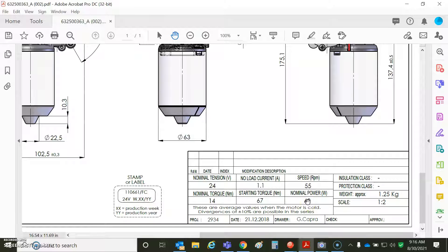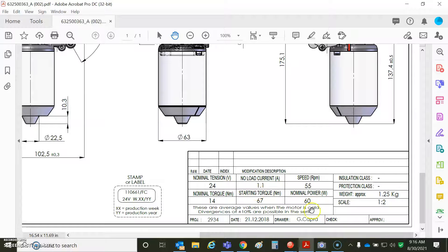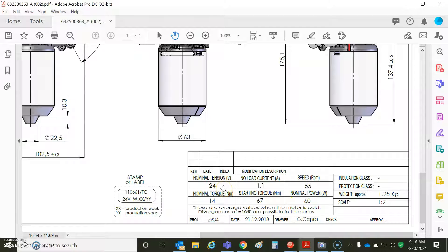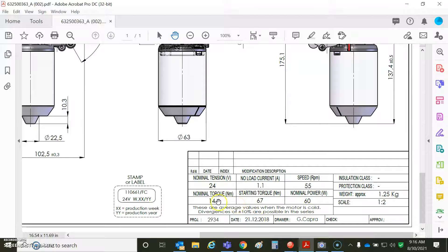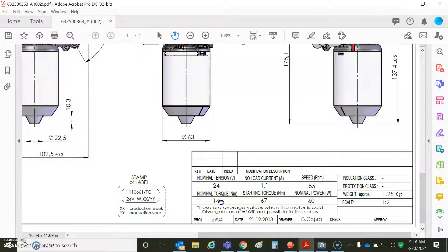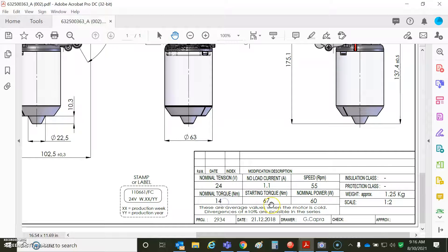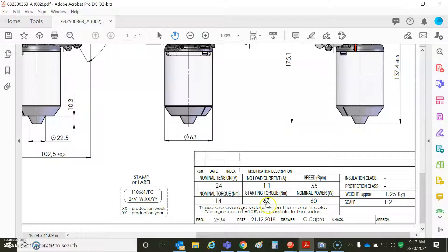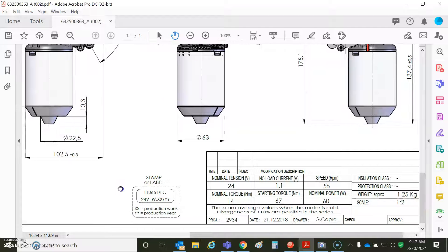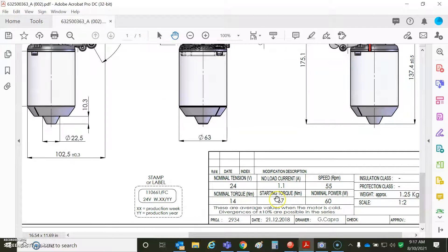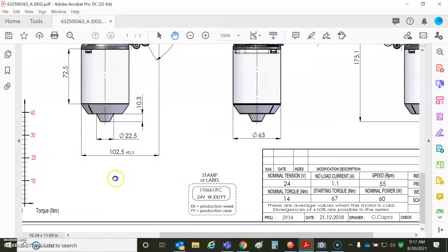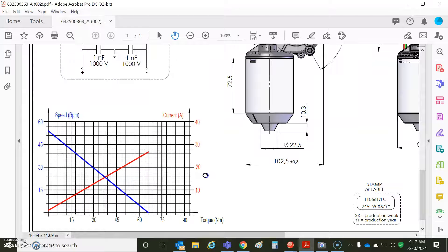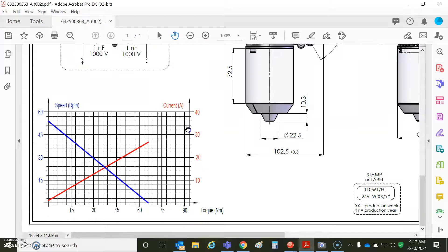Maybe this is for an elevator or something, so while you're lifting the mass, watch the current. Make sure you don't exceed the watts. That's volts times amps, speed times current, or speed times torque, or volts times amps out. So there's a nominal torque of 14 newton meters and a starting torque, 67 newton meters. That's just for a short period of time until things heat up.